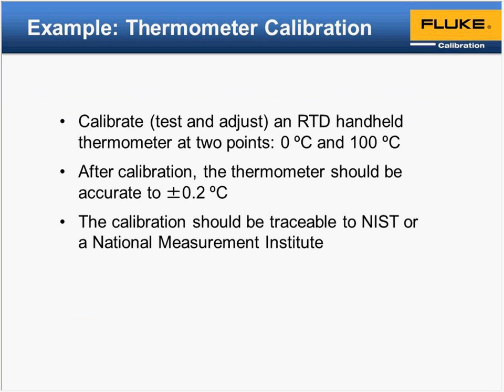All right, our example: we're going to calibrate, basically test and adjust, an RTD handheld thermometer at 2 points. The points will be fairly nominal, 0 and 100 C, to keep it simple for us. After calibration, the thermometer should be accurate to ±0.2 degrees C, and it should be traceable to NIST or an NMI. This is the criteria we're going to set up in our example, just to keep in the back of your mind: is this working, is this not working for what we're doing. We're going to review that as we run through the process and the techniques.